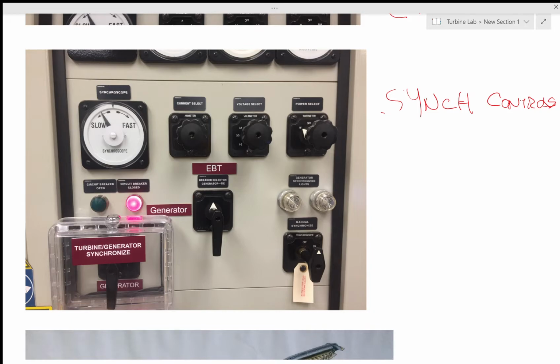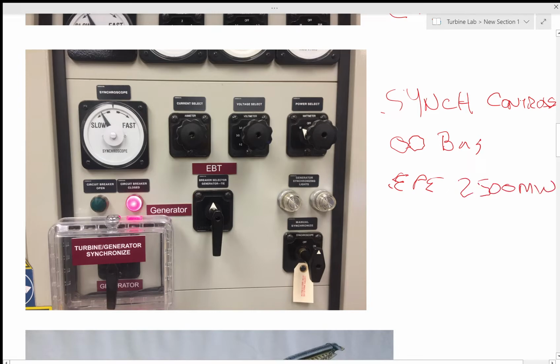These are the controls to synchronize our turbine to their system. If you go into power, you'll hear something called an infinite bus. El Paso Electric's system is, let's say, about 25,000 megawatts. They make that much power and put it on the system, and everybody in the region uses it. NMSU's power is 4.5 megawatts. So EPE looks like an infinite bus to the New Mexico State University turbine.